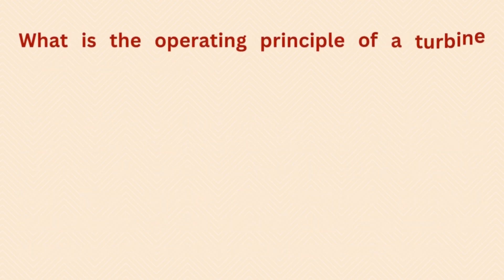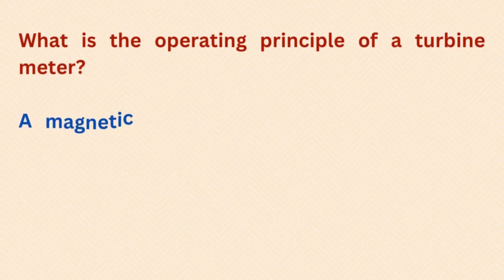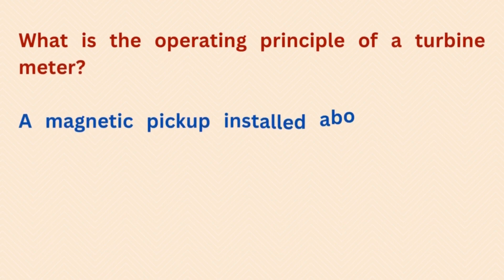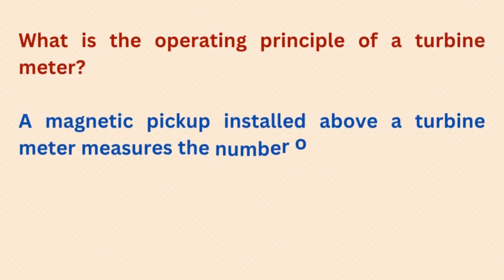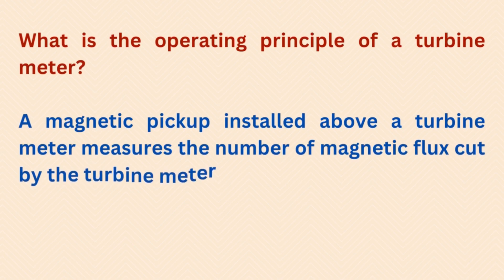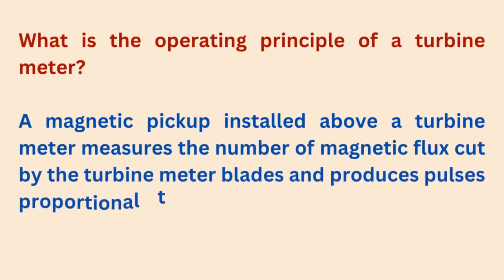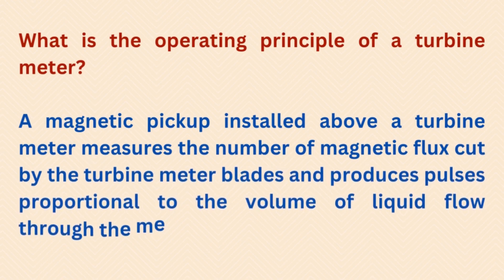What is the operating principle of a turbine meter? A magnetic pickup installed above a turbine meter measures the number of magnetic flux cuts by the turbine meter blades and produces pulses proportional to the volume of liquid flowing through the meter.